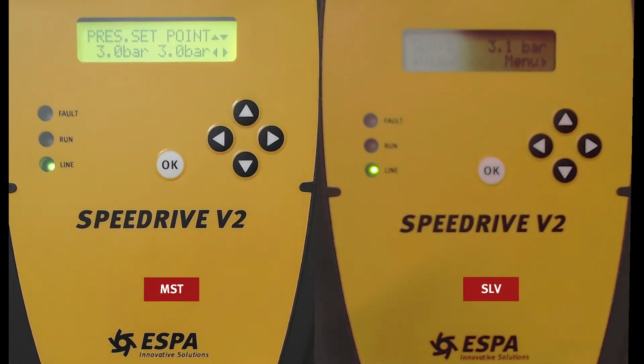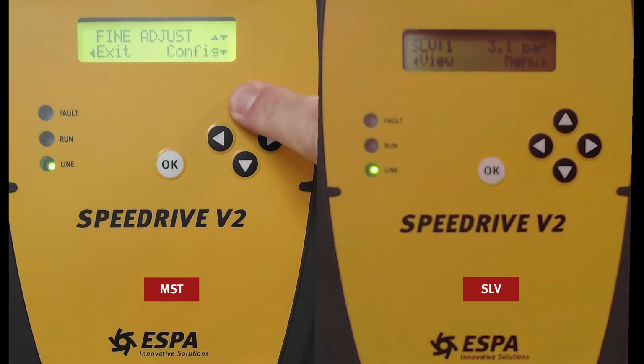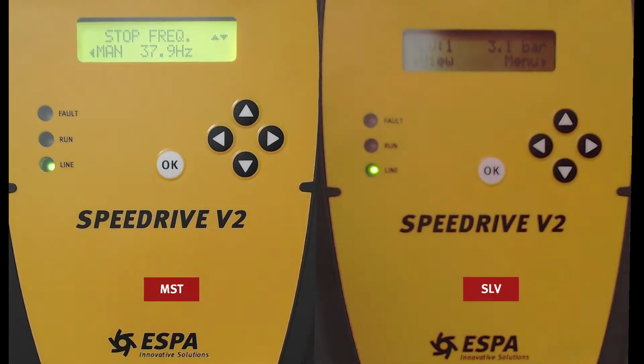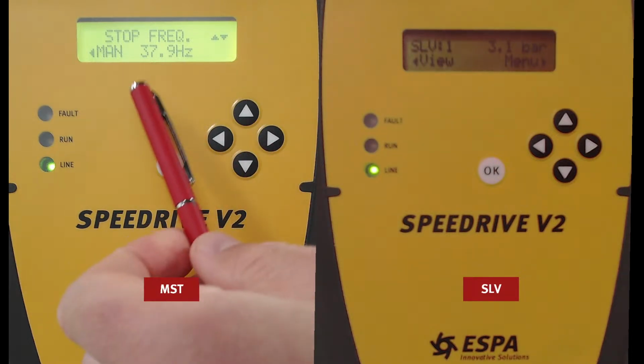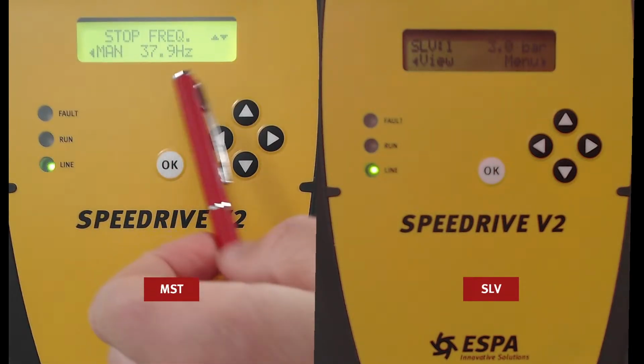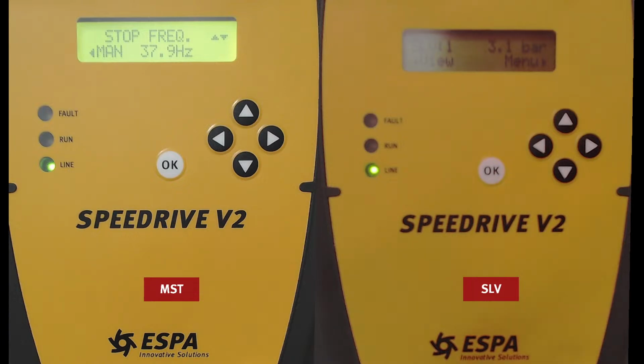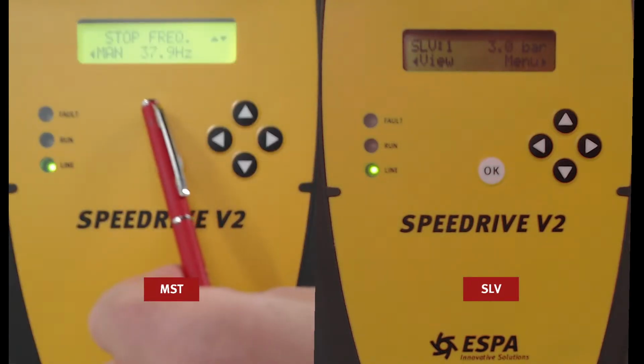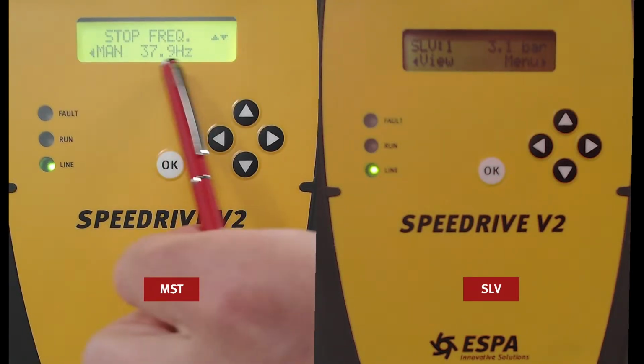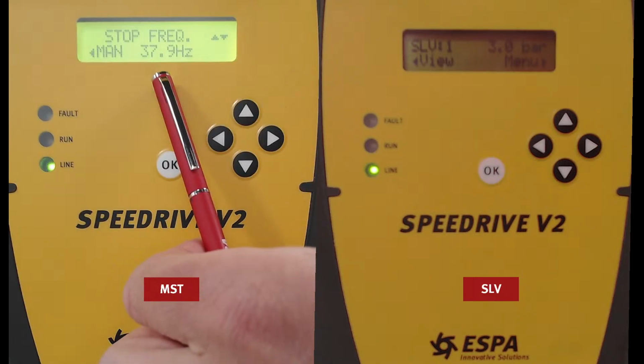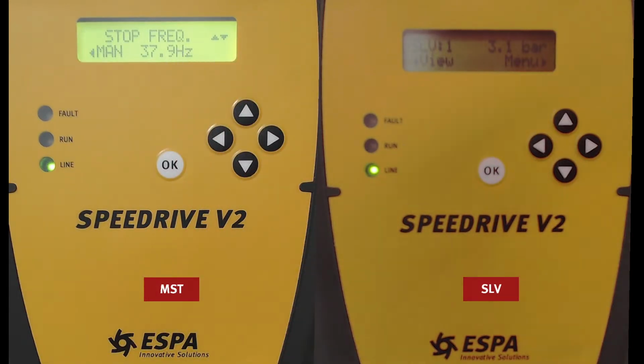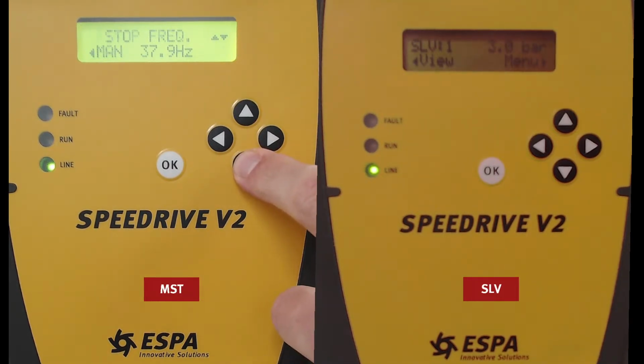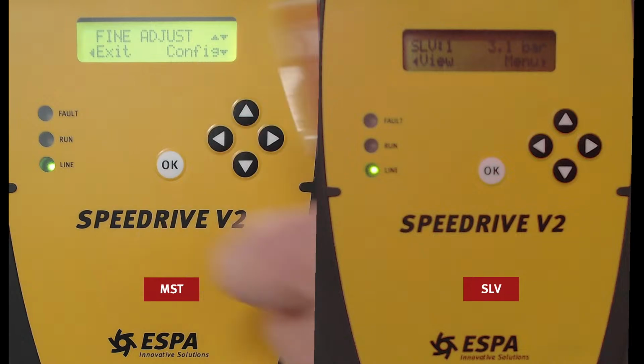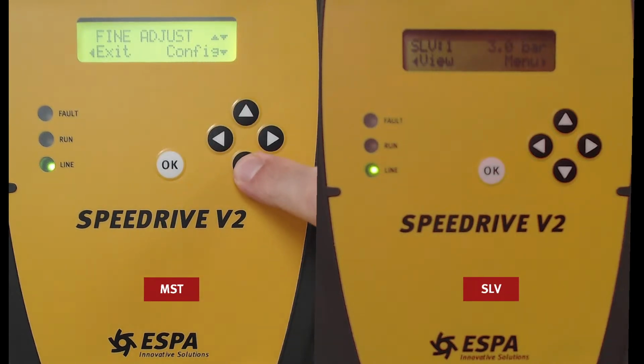We already talked about the duty point. This is the desired pressure that we want to maintain all the time. Stop frequency. This frequency is calculated automatically, and it's a very important parameter because it tells the VFD or Speedrive at which frequency it has to stop the pump when we have no flow or all the valves are closed. Fine adjustments, these are more advanced.